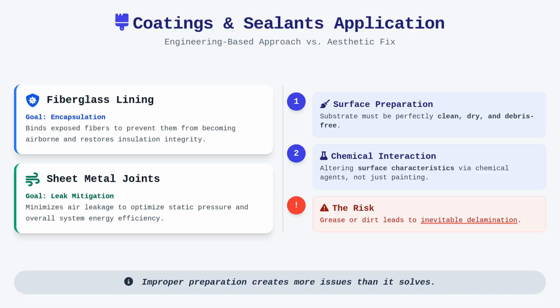Applying coatings and sealants is a practice that requires a measured, engineering-based approach rather than a simple aesthetic fix. When we discuss sealants, we are primarily concerned with two scenarios: the repair or encapsulation of damaged fiberglass lining and the sealing of mechanical joints in sheet metal ducts. In the case of damaged fiberglass, an encapsulant is used to bind the exposed fibers to prevent them from becoming airborne, effectively restoring the integrity of the insulation.